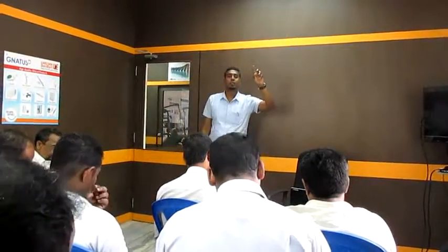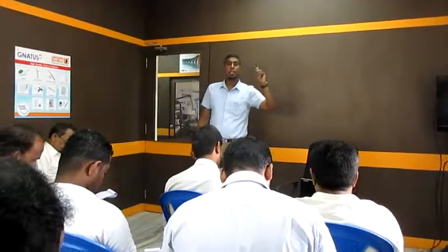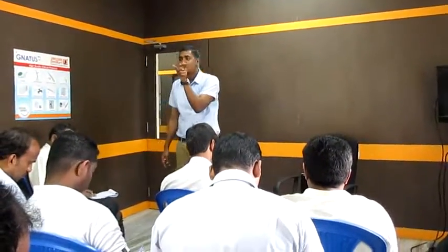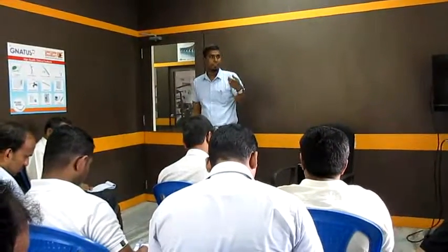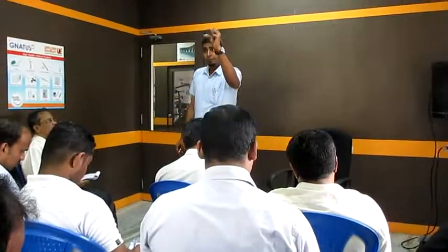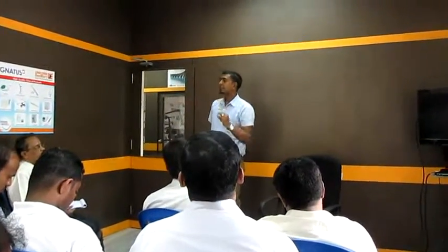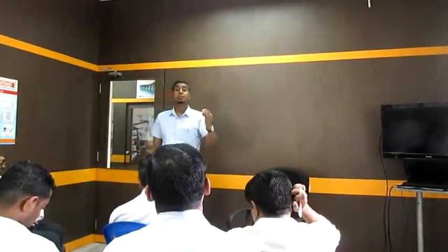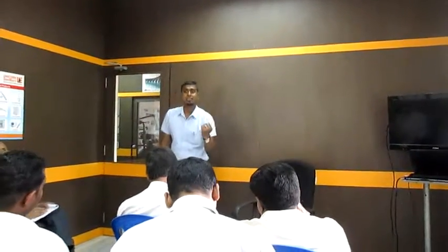And this gentleman is right, it controls the sharpness of the image. But sharpness doesn't make as much sense to you, blurring you will understand. The smaller the focal spot, the better the sharpness. The bigger the focal spot, the sharpness would be lesser.